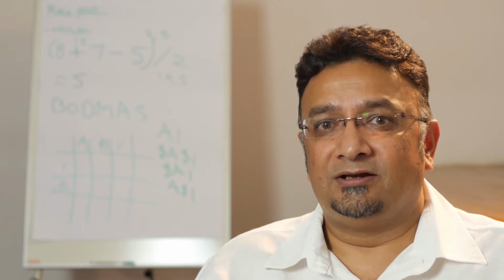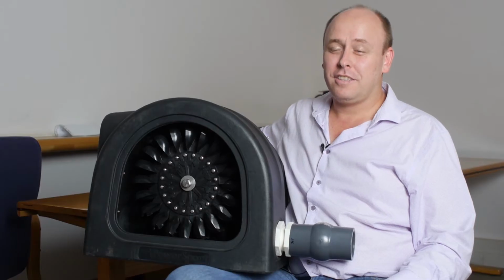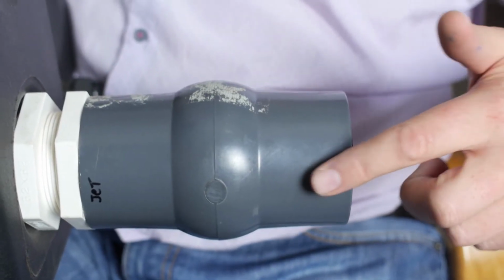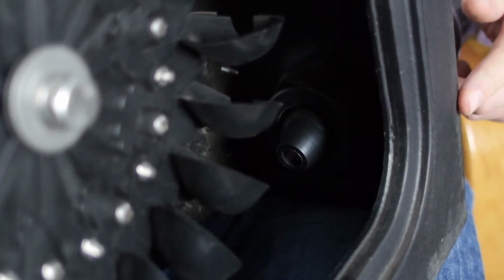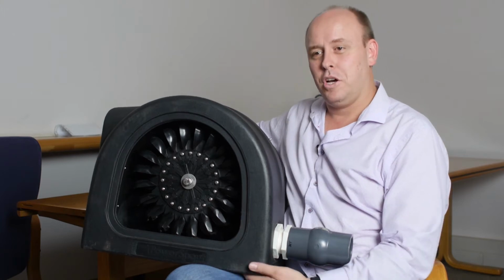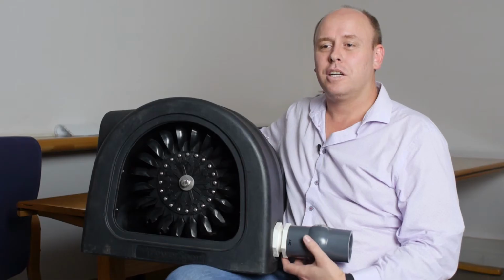As we completed that, we also followed up by looking at micro and pico hydropower units, etc. And in Durban, we implemented two very small pico units. This is one of the technologies that we used in eThekwini Municipality in Durban. This is a Pelton turbine, only 1 kilowatt. The water would enter the turbine through this pipeline. It will be forced through a nozzle. The nozzle then increases the velocity of the water that hits the buckets, and that would in turn turn the turbine. The water from this would then fall straight into the reservoir through the opening here at the bottom. A very small unit, but there is still application for that in the conduit hydropower environment.